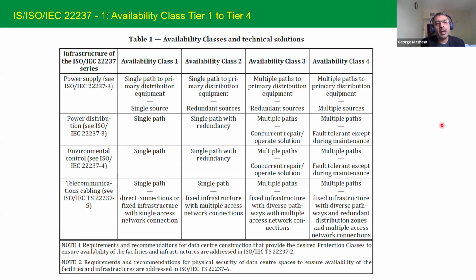Now coming to availability class 2 or tier 2, which again comes with single cooling or single power supply towards the load. However, the equipment supplied is configured as N+1. Let me explain a little what N is. For example, say we have a 500 kilowatt UPS requirement, a 500 kilowatt load requirement. We can split this 500 kilowatt into 100 kilowatt times 5, or let's say 250 kilowatt times 2.